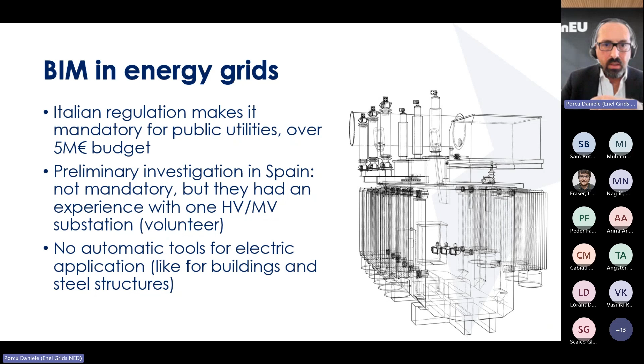I will go later into this point. Let me summarize the design phases. Before I mentioned the four phases: planning, designing, building, and operating. Actually, the outcome of the planning part is a sort of preliminary design. For example, I need to build a primary substation with 2 transformers, only 1 high voltage line, and 5 feeders in medium voltage as an exit. This is a functional pre-requirement, so we need to build this kind of power plant.